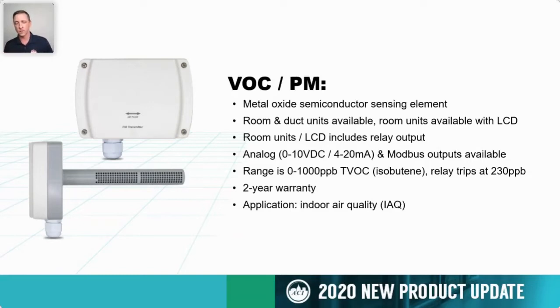And the reason why we're doing that is because while occupancy can increase VOCs in a space, and it's often that the higher the occupancy of a given space is, the higher the VOC concentration, it's not always the case. They're not completely tied together. You can have VOCs present in a space that has very limited or no occupancy. VOCs can be present from cleaning materials, from paint on walls. It can be present in off-gassing from new carpeting and things like that. So that's why our device is giving a true or total VOC output and not a CO2 equivalent.